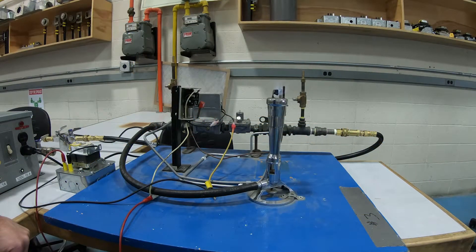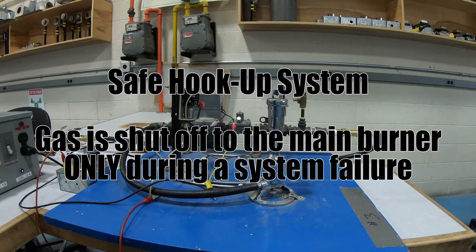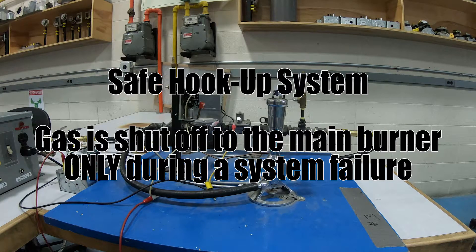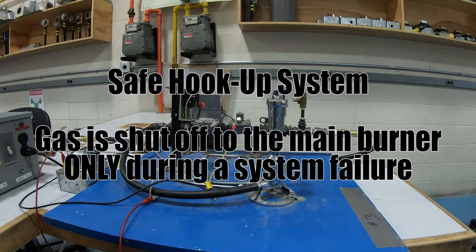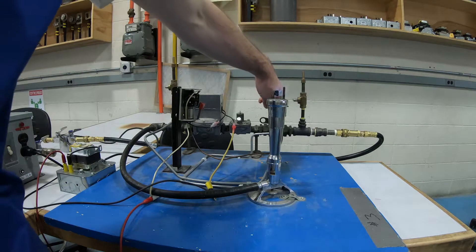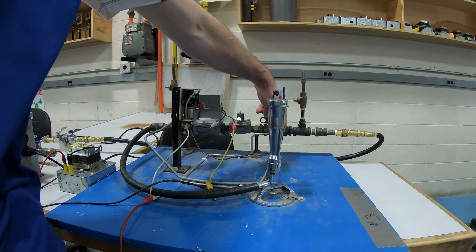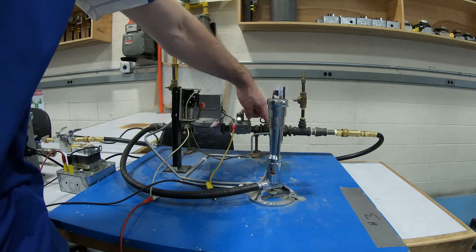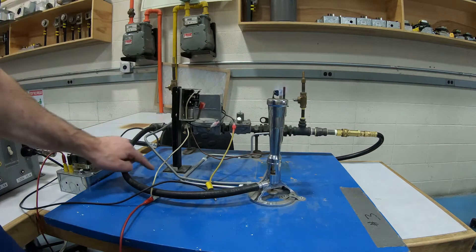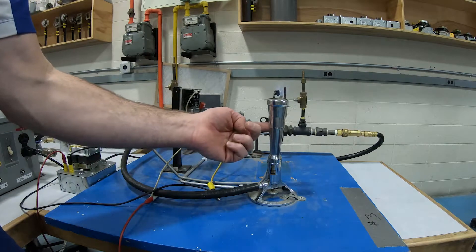Now the next type of gas train setup is like this. We call this a safe hookup. Now the reason why we don't call this 100% safe like the other one and just a safe hookup is because I have my pilot assembly or the gas going to my pilot light joined in here with a manual valve. And if you follow the pilot tubing, it just goes straight to the pilot light.